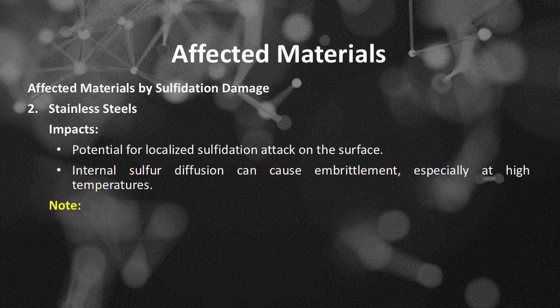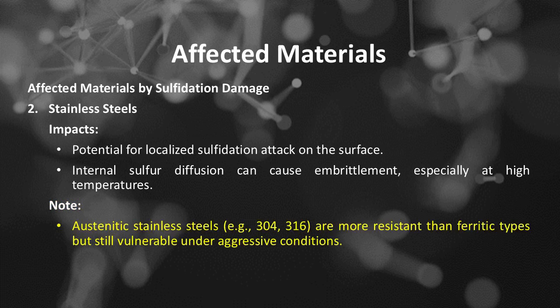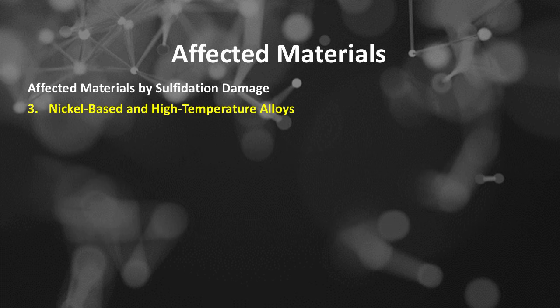Note of affected materials by sulfidation damage to stainless steels. Austenitic stainless steels, such as 304, 316, are more resistant than ferritic types but still vulnerable under aggressive conditions. Number 3 of affected materials by sulfidation damage is nickel-based and high-temperature alloys. Description of nickel-based and high-temperature alloys.